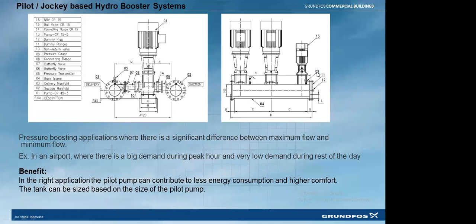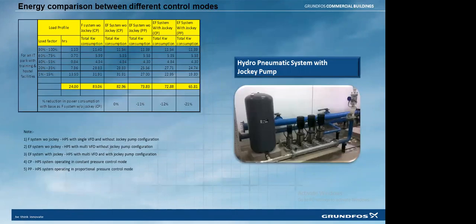Still, people will have a thought: sir, I already have a pressure tank. The pressure tank comes into the picture only when the load goes below 2% or 1%, a very, very minimum nominal requirement. Only to serve that requirement will the pressure tank come into operation. Otherwise, your pump will keep on running. To avoid that, we can have this pilot pump to improve the system efficiency. Next slide, please.